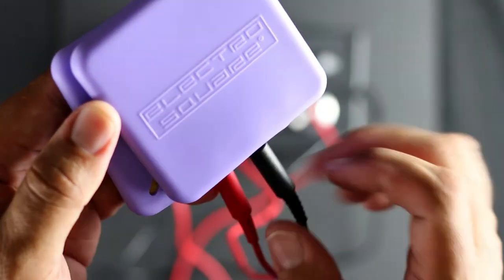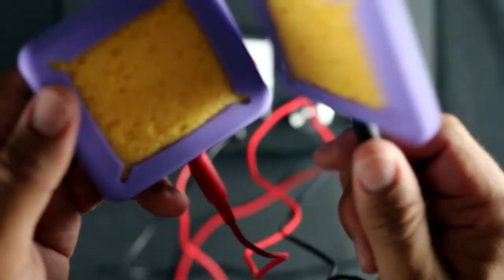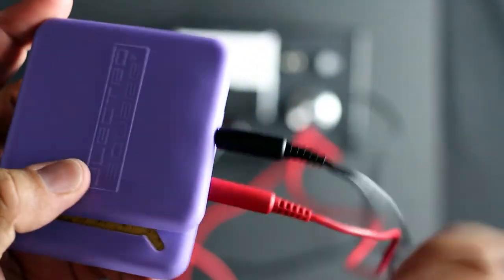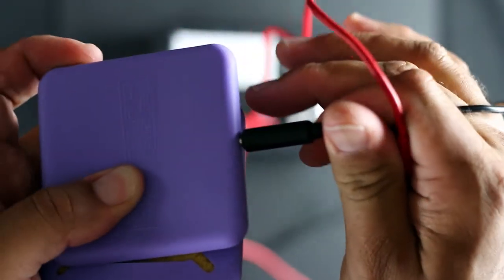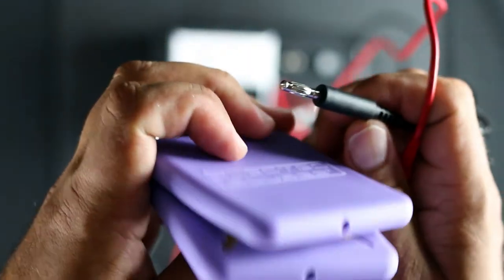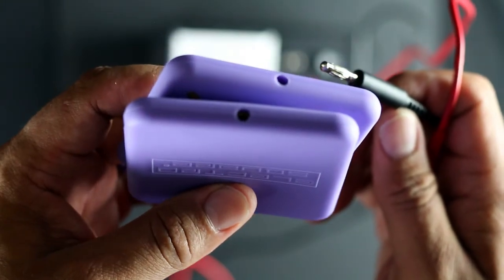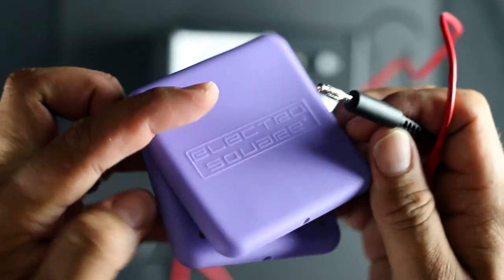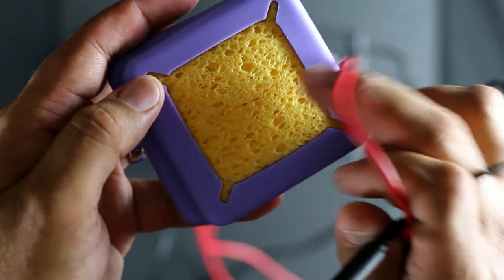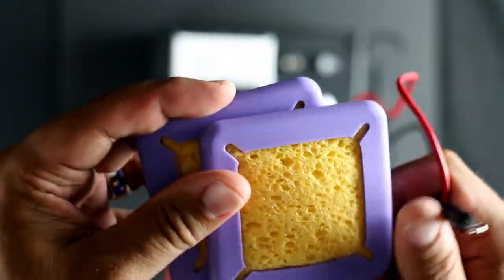Another thing that's important for care and maintenance of your electrodes and cables is to make sure that after each stimulation session, you remove the cables. You can leave the electrodes as they are. You don't need to disassemble them. You don't need to remove any of the parts internally. Every six months or so, you need new sponges, but that's just about it.